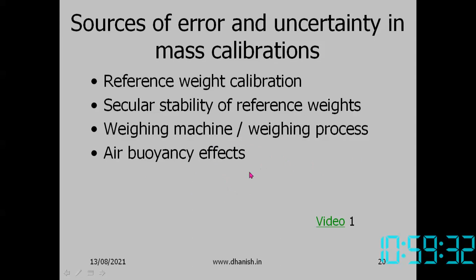Depending on the atmospheric pressure, which depends on weather, sometimes suddenly we'll have a depression, so low atmospheric pressure. Then the calibrated mass changes; the weight changes. If you're comparing weights and the volumes are the same, it will not be affecting. But if the volumes are different, then buoyant forces will be different. For example, in our deadweight pressure gauge tester in our lab, when calibrating pressure gauges, we have to correct for air buoyancy effects. Of course, only for high accuracy gauges it is important. Normally in our lab experiments, we don't consider this.